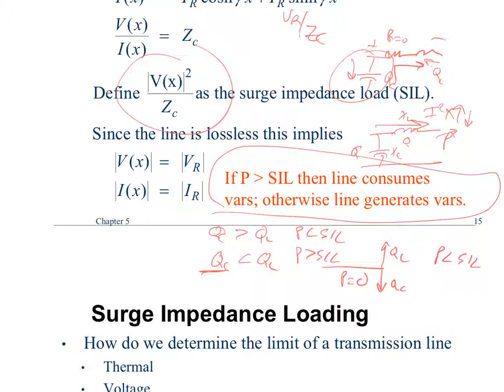And if you look at what we do in Chapter 6, we do what's called a load flow. It's the official title of it. What is the ultimate output of a load flow? The voltage. If the voltages are within tolerance, then that's usually a pretty good sign you're okay. You still have to do some more work, but you're just constantly running load flows to go ahead and determine that.